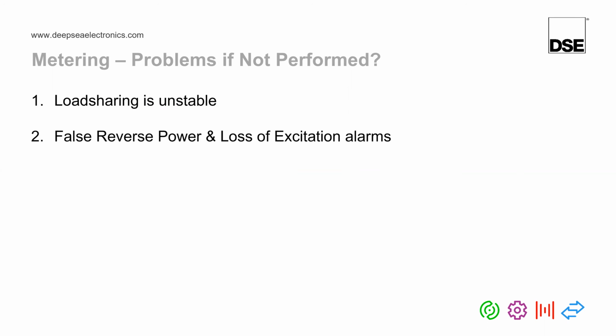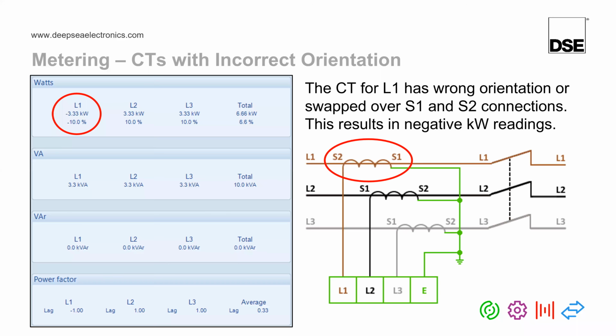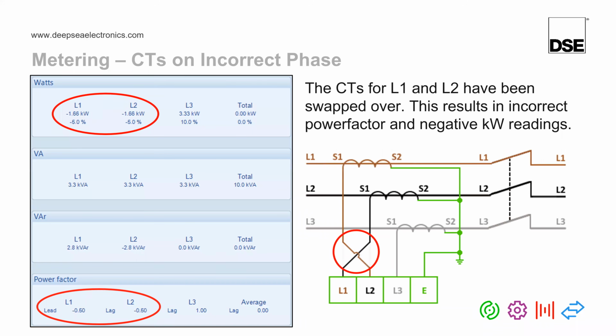Another fault that we potentially could end up having here is false reverse power or loss of excitation alarms. Reverse power being excessive negative kilowatts and loss of excitation being excessive negative kVAR. Again, going to the previous slides, you will see here we have negative kVARs on one phase, even though it should be 0, and negative kilowatts.